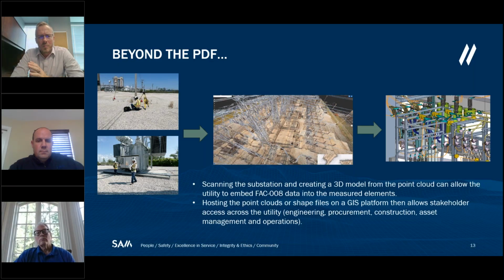With a point cloud, the people in the field collecting FAC-008 data are all cross-trained to scan a substation. If you collect a point cloud, you can host it on a GIS platform, or GIS Online, so all your stakeholders inside the utility can access that point cloud and see the equipment that needs to be replaced — procurement, engineering, construction, operations, asset management groups. It becomes a great platform to develop your equipment replacement project to get your facility rated correctly and avoid derating your line.